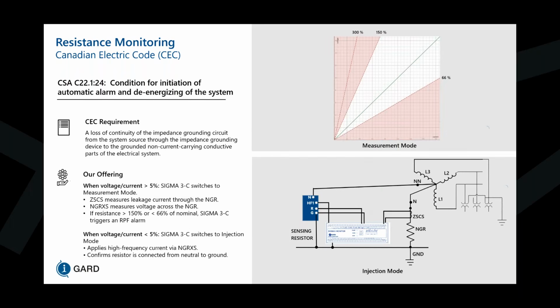When there's a loss of continuity, our high frequency signal is shown there. If we get an open circuit here and we don't receive our signal back, then the relay has a counter inside and it just gives it some time, and then it indicates that there's an open circuit if it never gets the signal back.